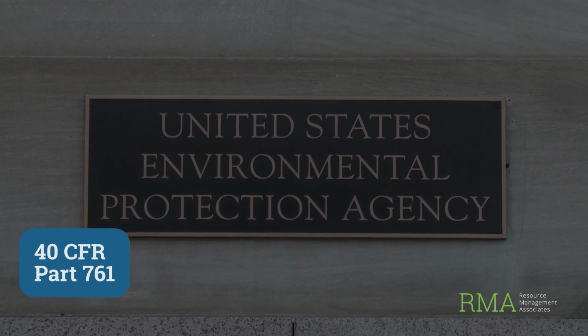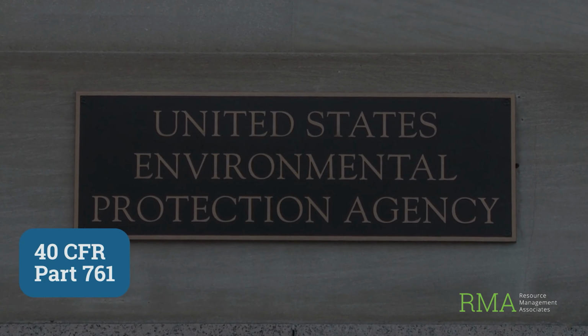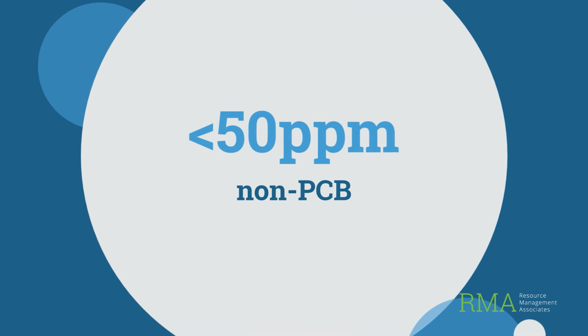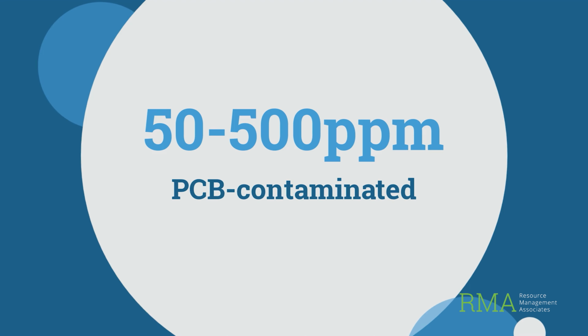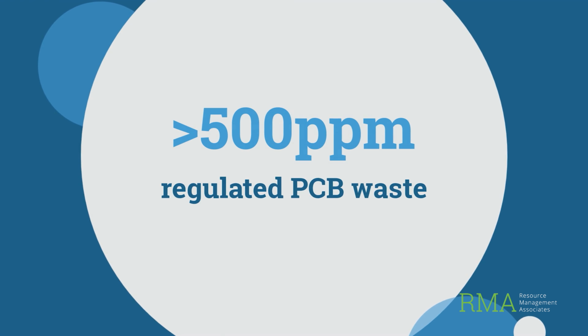So who regulates PCBs, and what actually counts as contamination? That's EPA under TSCA, specifically 40 CFR Part 761. The key number is this: 50 parts per million. Below that, it's generally considered non-PCB. Between 50 and 500 parts per million, it's considered PCB contaminated. And above 500 parts per million, that's PCB regulated waste, and cleanup rules get real strict real fast.